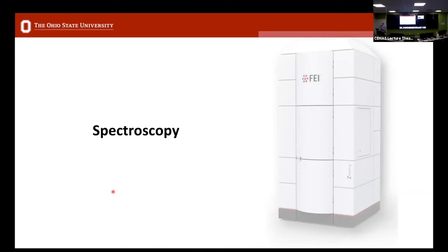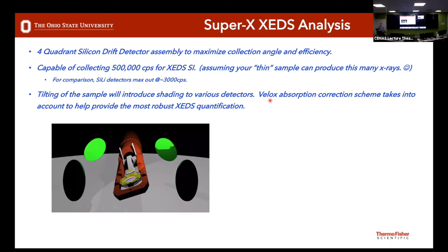Moving to spectroscopy — I want to talk about SuperX EDS and EELS briefly. Our SuperX system has the TEM holder and sample surrounded by four detectors filling the space around the sample, allowing half a million counts per second. For thin samples you can see the X-rays coming out because you have a nice solid angle, and for thicker samples you can still collect all those X-rays for really good quantitative counts. We use VELOX software, Thermo Fisher's proprietary software, which has a nice EDS processing tool and absorption correction scheme.